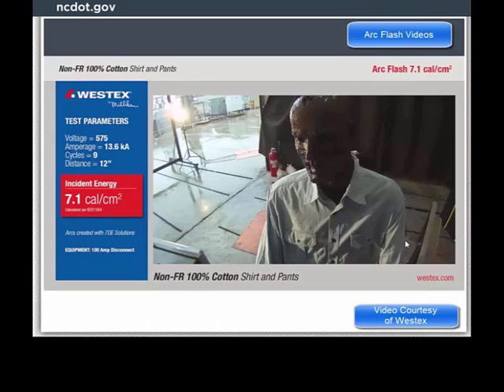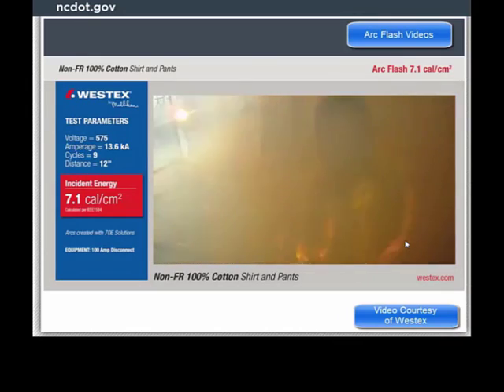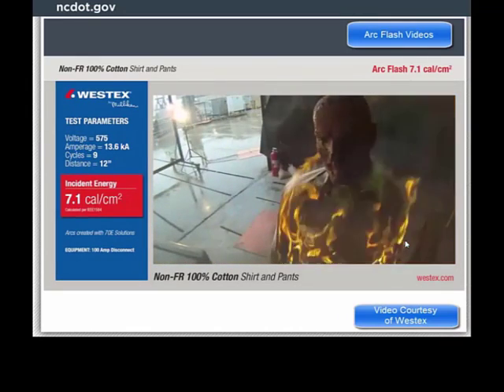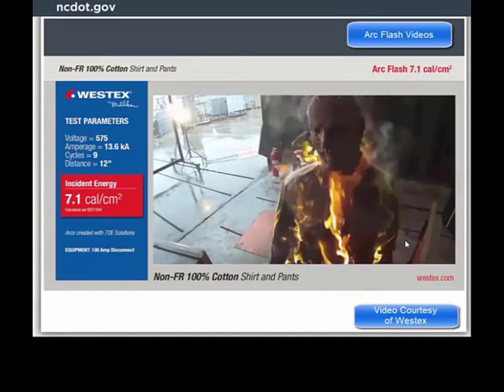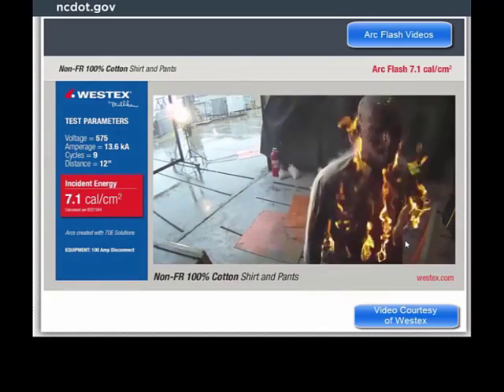With this arc, we had a camera positioned directly on top of the disconnect, giving us a head-on look at this arc and fire. Look at that. As the smoke clears, the entire shirt is on fire, waist up. Our firefighters come into the scene and pull the mannequin back. You get an even better look at how extensive and how aggressive this fire is.